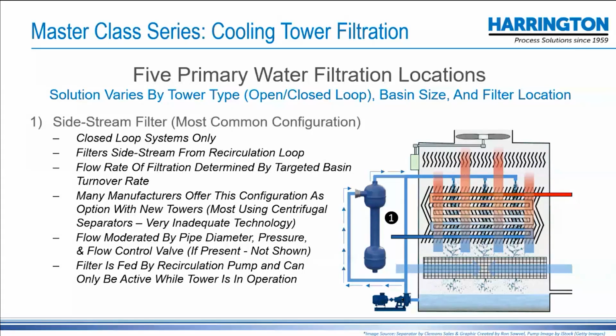And I just have to say up front, this is the very worst possible application. It's the very worst for a couple of reasons. I'll talk about the centrifugal separators. We sell centrifugal separators, and there are places where they're perfectly suitable. This is not one of them. But it is by far, if you go to brand new cooling towers and they have a filter on it, most likely it's not going to be a filter, it'll be one of these. So even if you encounter an existing cooling tower with one of these, the end user, the customer, would be best served by taking that out and putting in a different kind of filter.